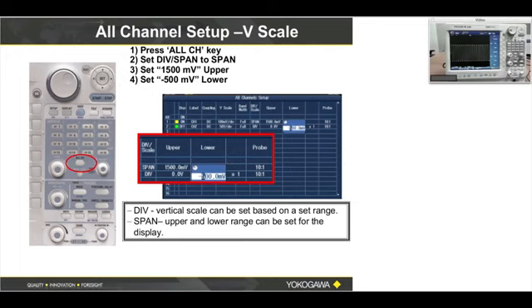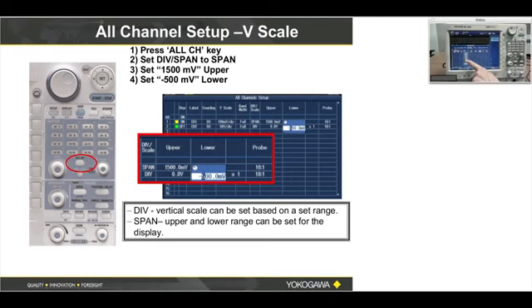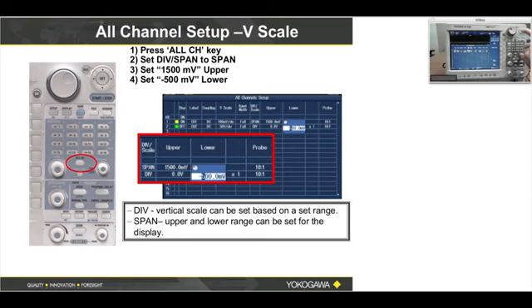Let's go back to the PowerPoint presentation — we're going to discuss all-channel vertical scale. Press the All Channel button, then press soft menu button number one, Setup. Using the big knob, select vertical scale on channel one, then press Set and select a value from the drop-down box. I'm going to select one volt per division. The point is to get some experience turning the shuttle or jog knob and using the set button. As long as everyone has that concept, we'll move on.